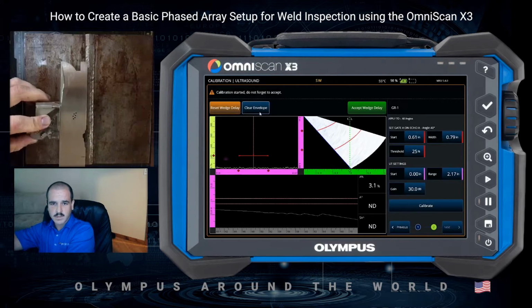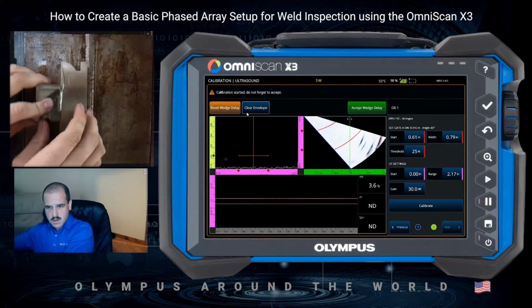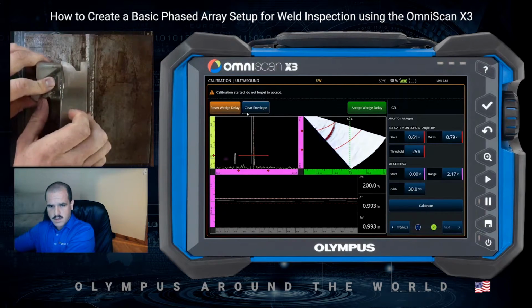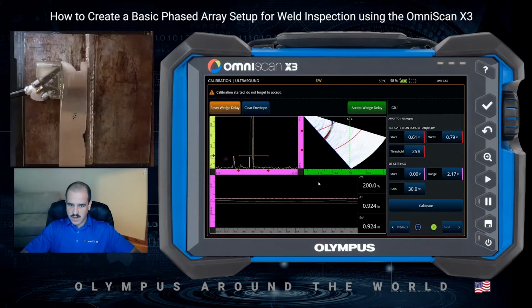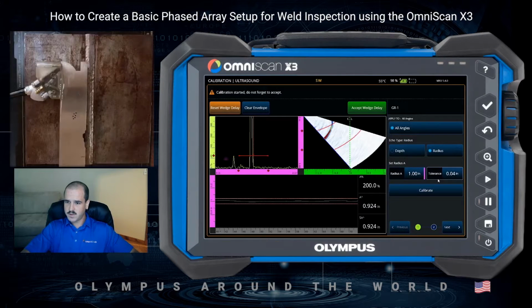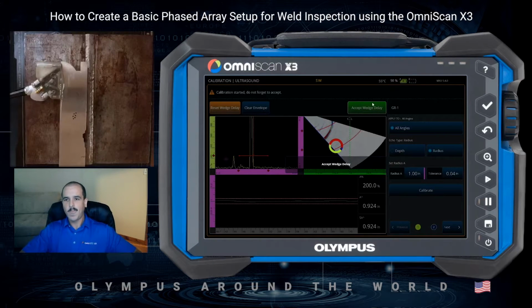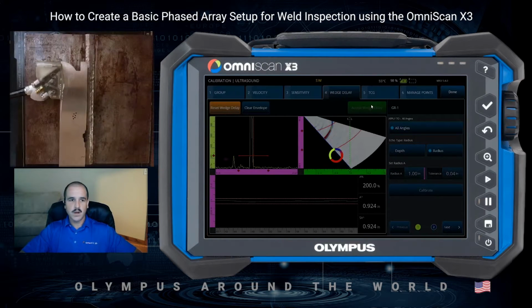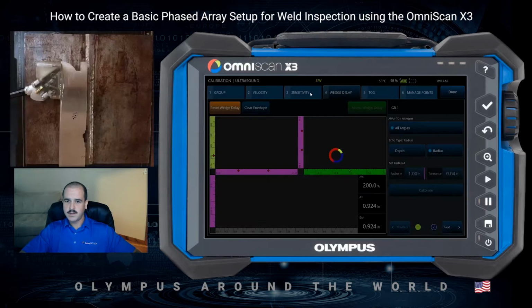Go ahead and clear my envelope. There we go. So wedge delay checks out good. We're within our tolerance here that we can set on the first page of 0.04 of an inch or 1 millimeter. So now I'm going to accept our wedge delay calibration. And then we'll move on to the sensitivity tab.